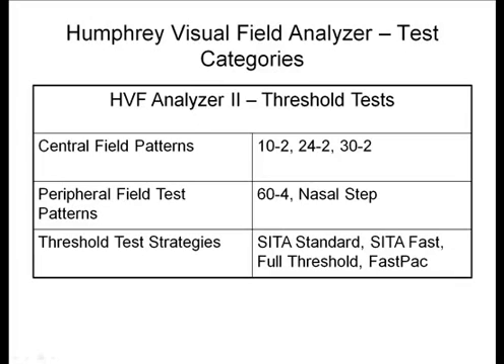There are a number of different threshold tests and strategies. The central field patterns are typically most common; the ones we usually order are either the 24-2, 30-2, or central 10-2 test patterns. For glaucoma, the 24-2 is usually the most commonly used. There are also peripheral tests, and a number of different test-taking strategies — either SITA standard, SITA fast, full threshold, or FASTPAC — all differing in the way that threshold is bracketed.